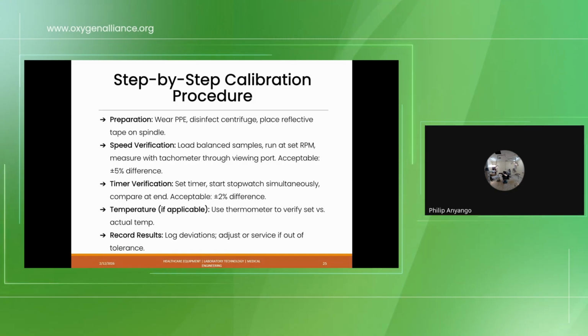Yes. I just wanted to chip in there. The centrifuge can go out of its speed because of wear and tear. What are the parts that you need to check first before you adjust the speed port? Check the brushes, the parts that wear. As Engineer Wanda has mentioned, mechanical and what have you. You check the parts that wear, check the brushes, check the balancing, and all those kinds of things which can wear out. Of course, with use, things wear out. That's why we need to do maintenance and service. And if you notice there's something to be replaced, you replace it with time.